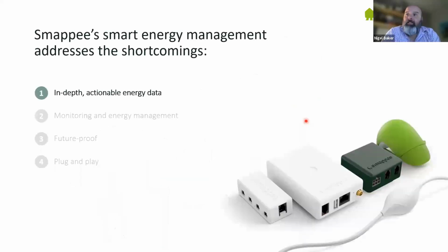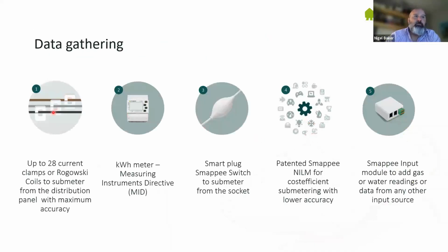From the Smappee devices, we get in-depth actionable energy data, and this data comes from current transformers. One of the unique features of Smappee is that we can get 28 current transformers or Rogowski coils on one device, which equates to 9 three-phase supplies, or 28 single-phase supplies, or a combination of either, as long as there are not more than 28 current clamps or Rogowski coils on the Smappee. We can measure from 100 milliamps up to 10,000 amps with the current clamps or Rogowski coils.